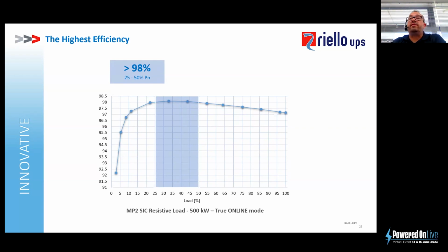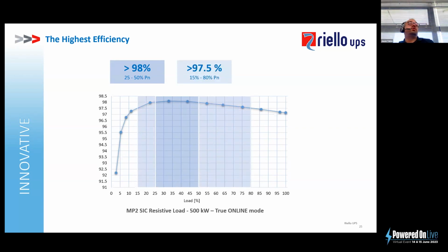Now, normally that would generally be higher up the load range. However, it's slightly different with silicon carbide. We can also see, however, that we are still greater than 97.5% efficiency for between 15 to 80% of the load range. And again, still further, we are greater than 97%, even from 10 to 100% load. So in terms of performance, it's extremely good. Now, one of the main things of this is that it is in online mode only. This is not in eco mode.